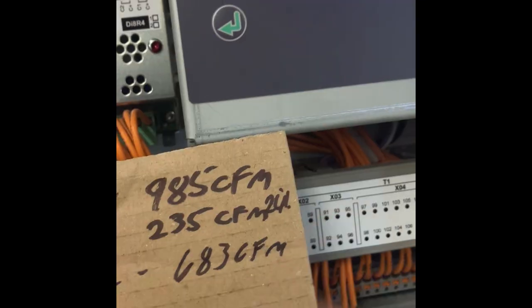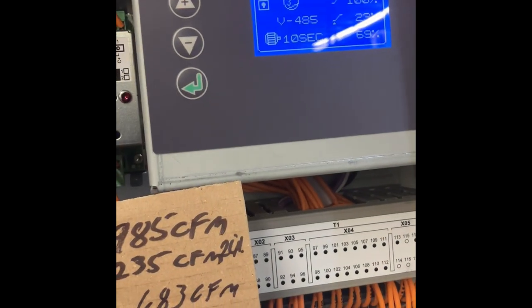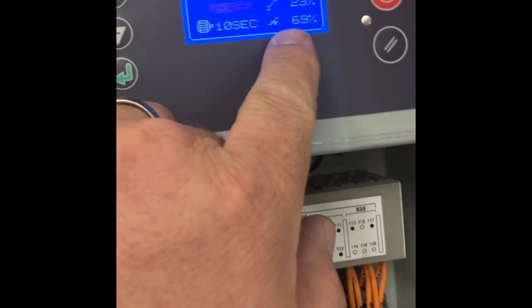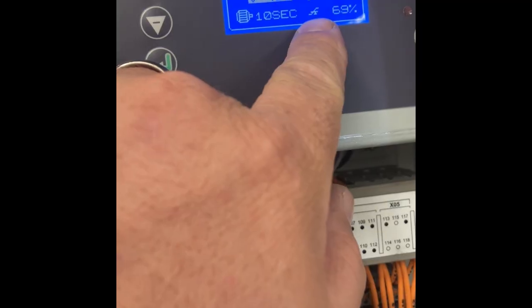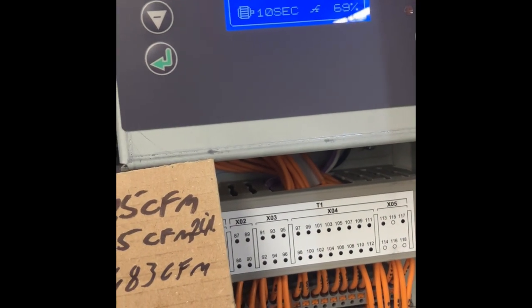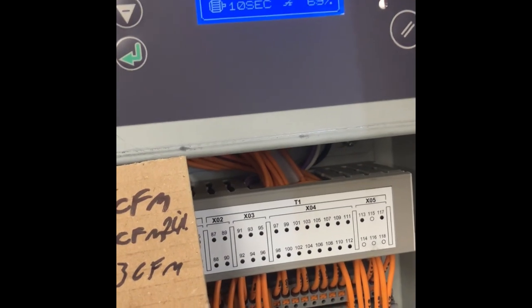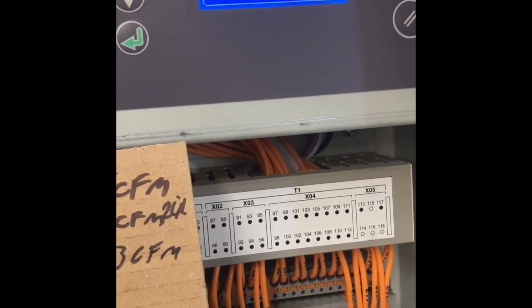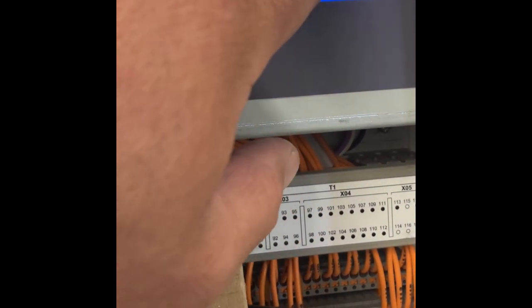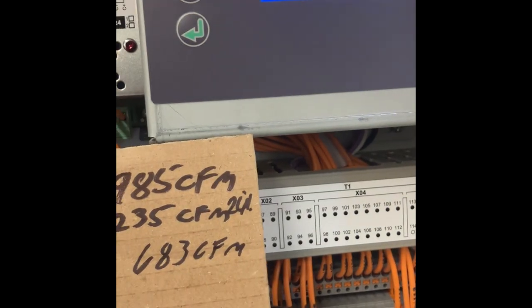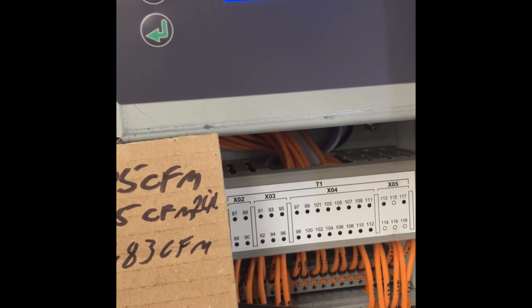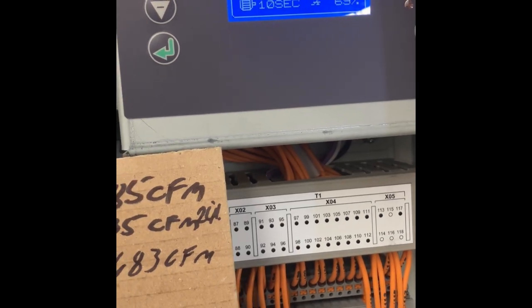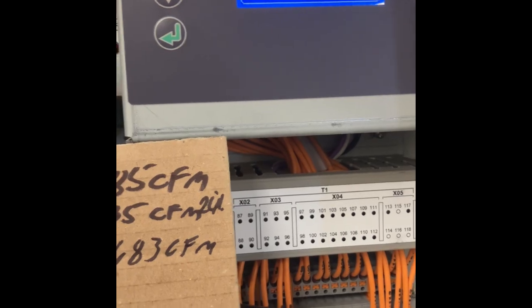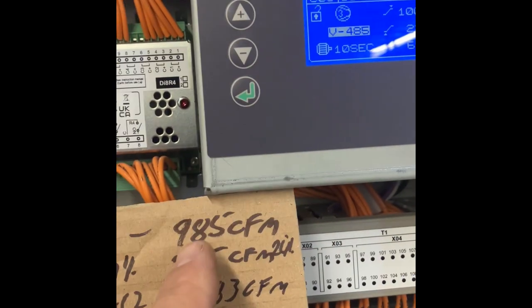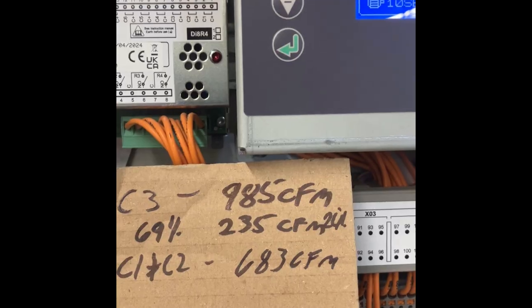That's why that number on C1 and C2 is 69%. This number, anytime you have a variable speed or variable capacity machine, is basically asking at what percentage of full load does it become more efficient to switch to a non-variable machine. Since my fixed speed machines are at 69%, if you're running this variable speed drive at 69%, it's going to be more efficient to just fully load a fixed speed machine. So that's what all those numbers are. Your biggest compressor is going to be your 100%, and everything else is based off of this number. So don't get that screwed up.